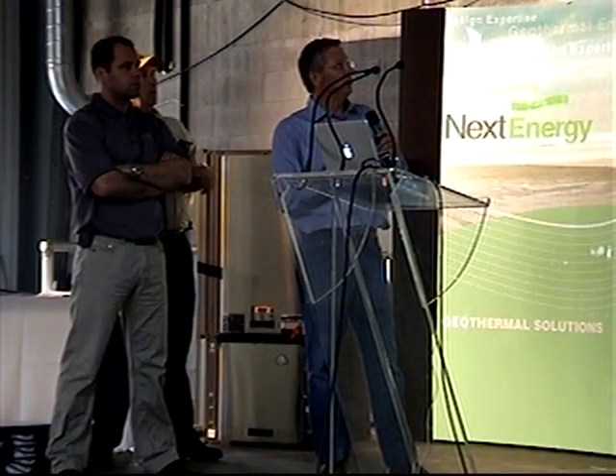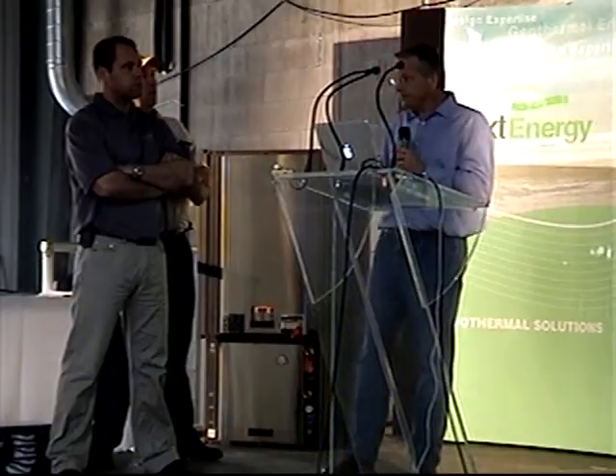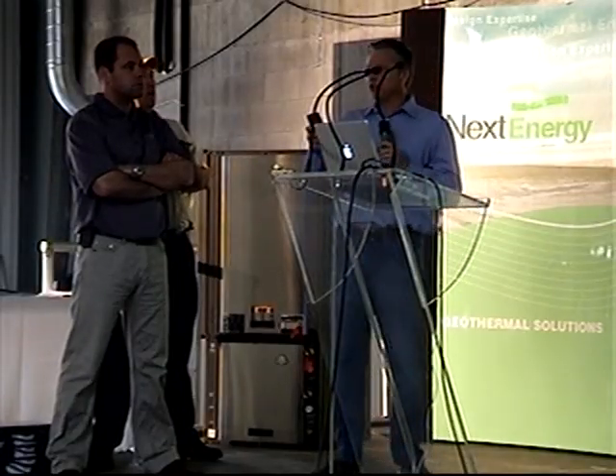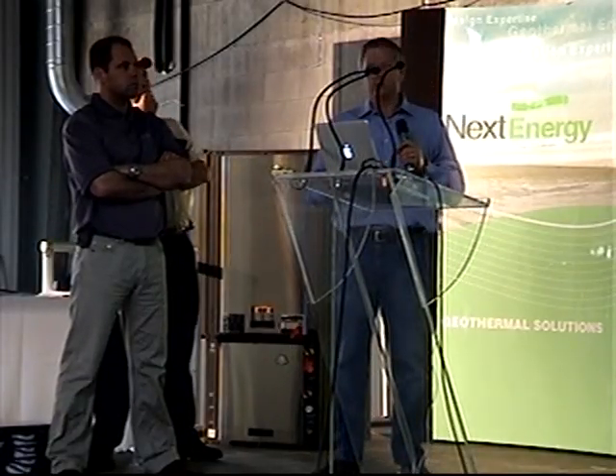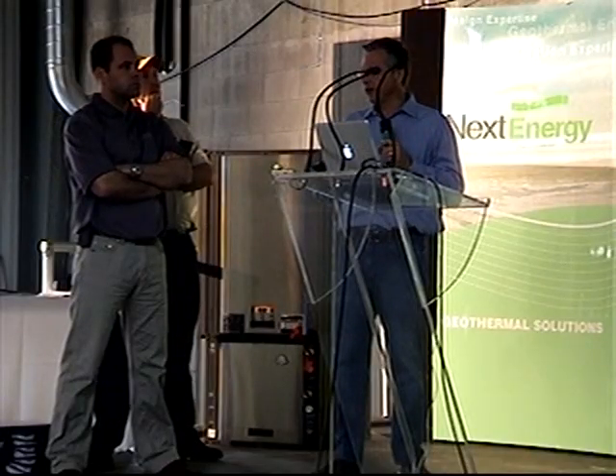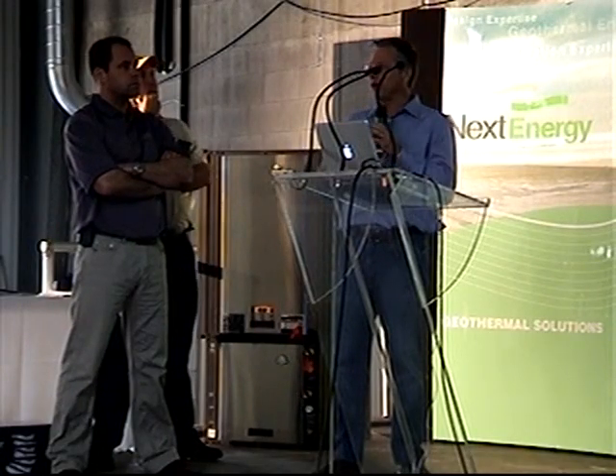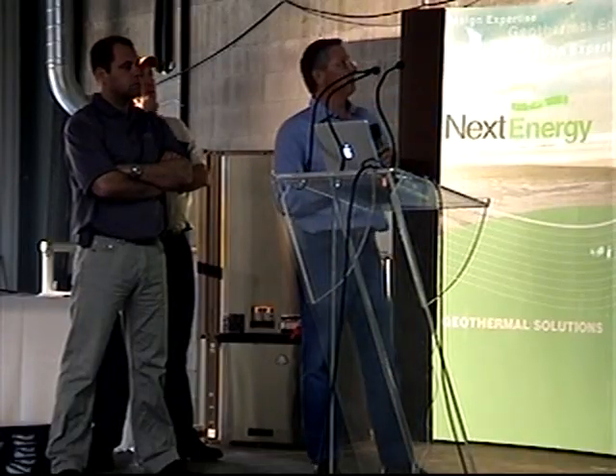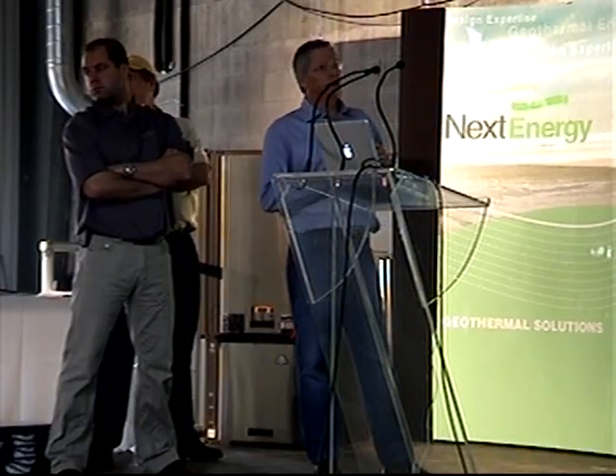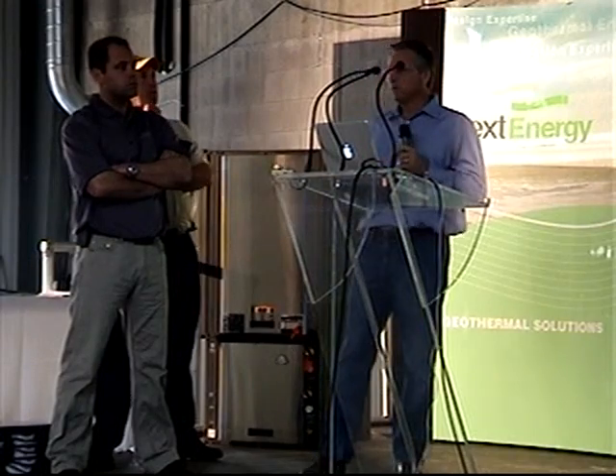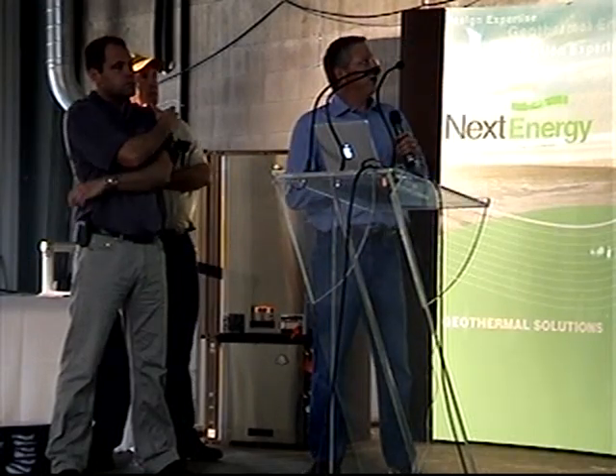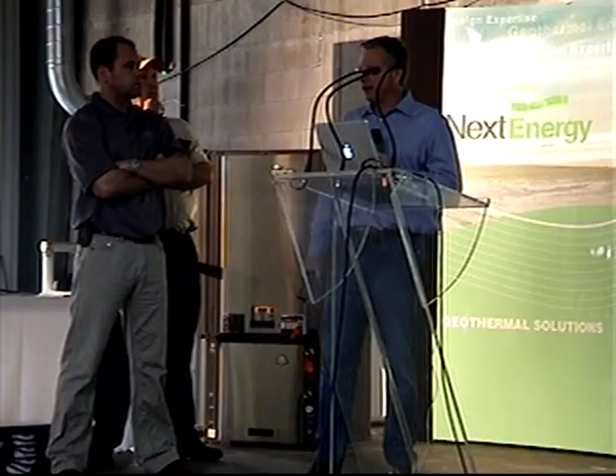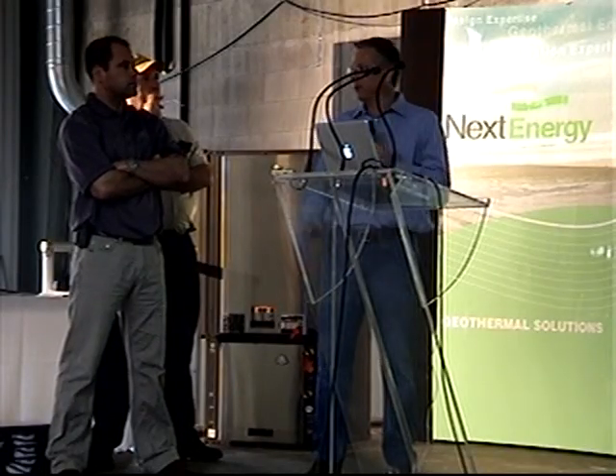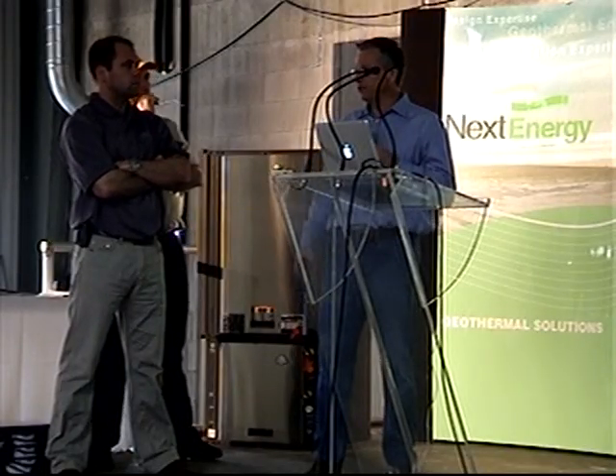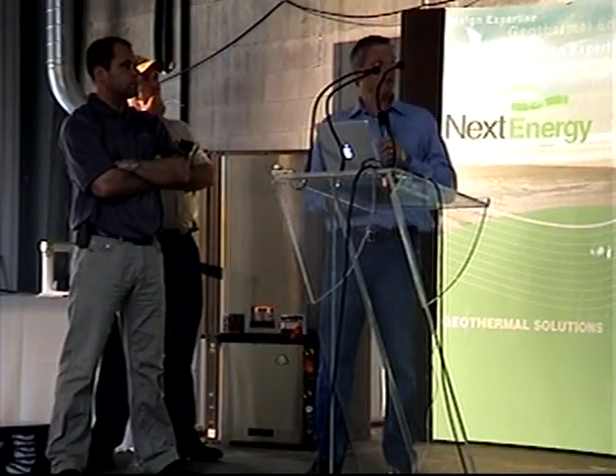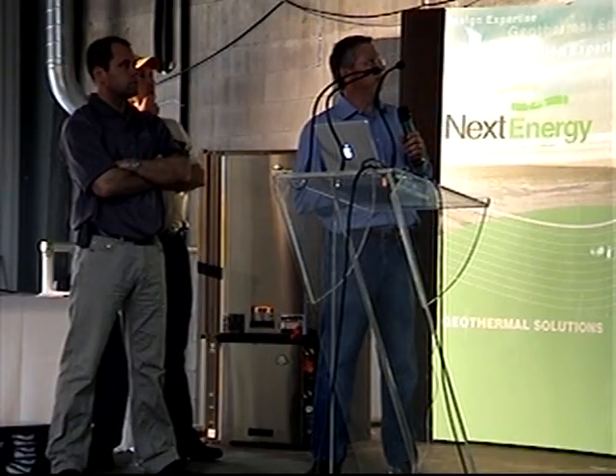It's worked really well. We have high and low voltage protection. If the voltage gets too high or too low, the unit will stop operating until that condition corrects itself. It's not really a lockout. It'll come back on when the voltage comes back in line. Yeah, it's in the board. And we had it pretty tight, and then we found out there's all kinds of crappy power out there, so we had to loosen things up a little bit because we had units with a lot of overvoltage stuff going on. So we kind of loosened the parameters a little bit.